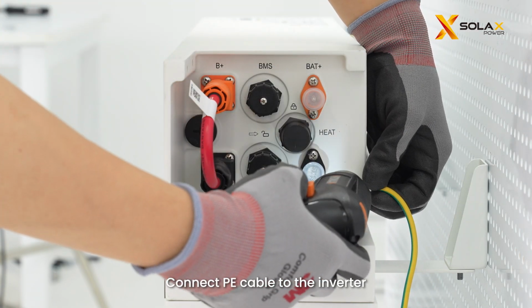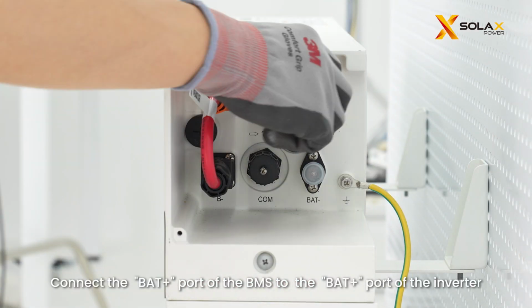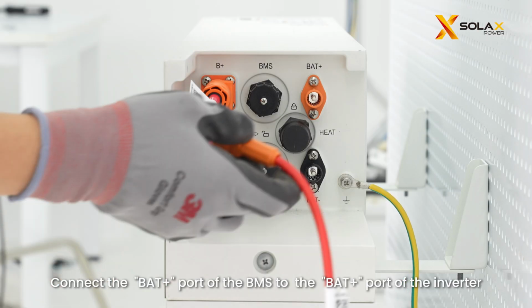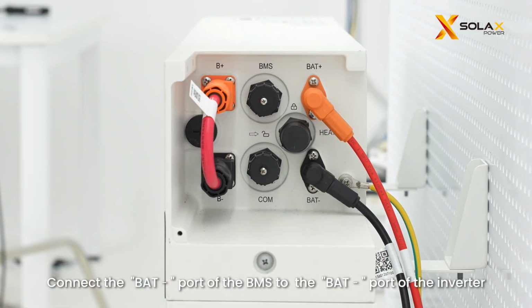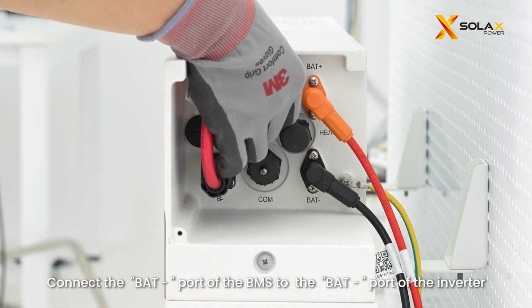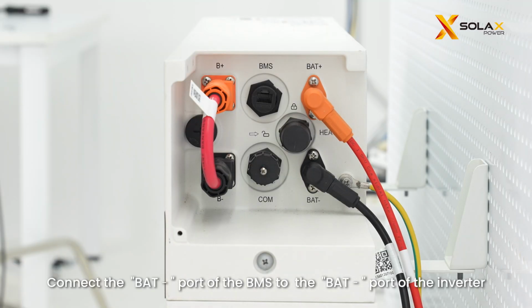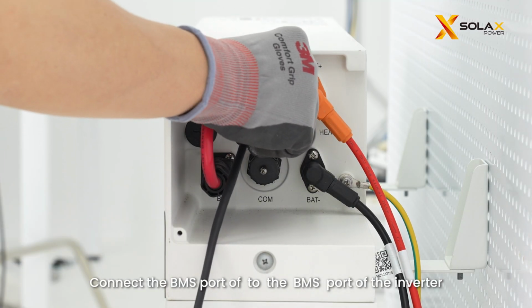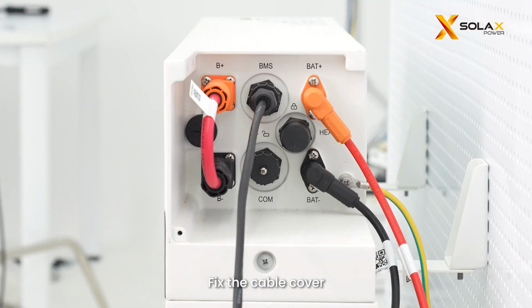Connect the PE cable to the inverter. Connect the BAT positive port of the BMS to the BAT positive port of the inverter, and the BAT negative port of the BMS to the BAT negative port of the inverter. Connect the BMS port to the BMS port of the inverter, then fix the cable cover.